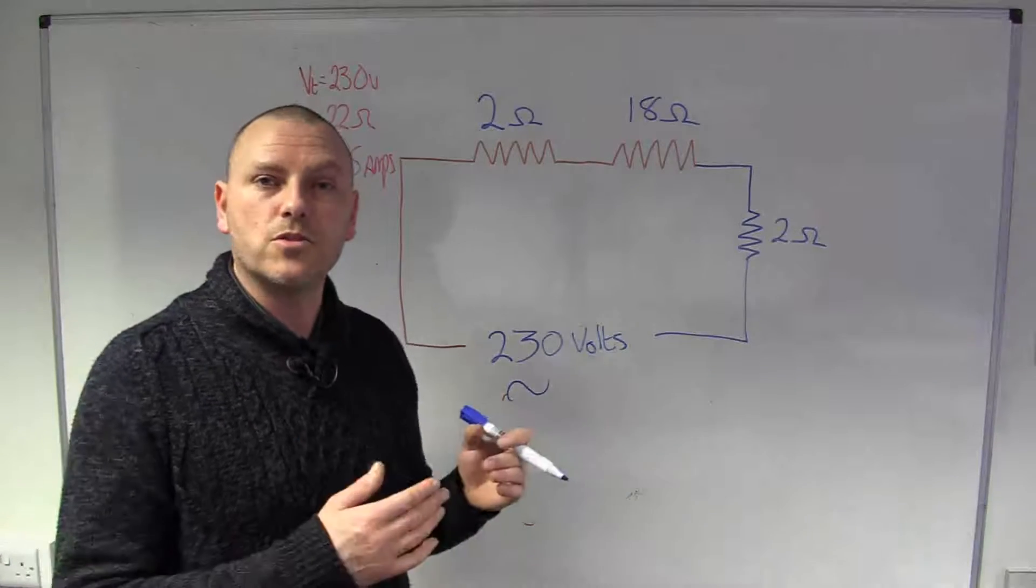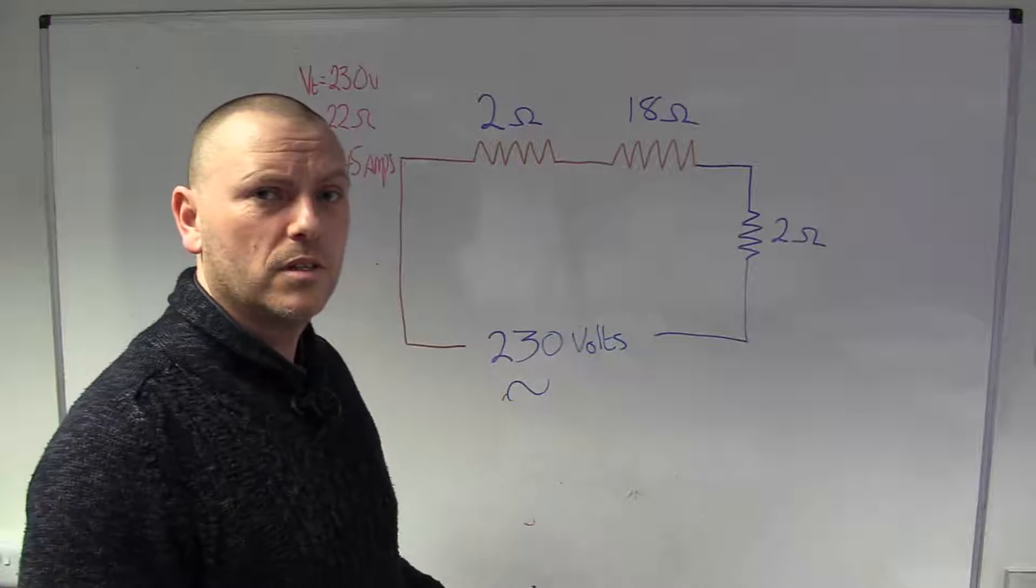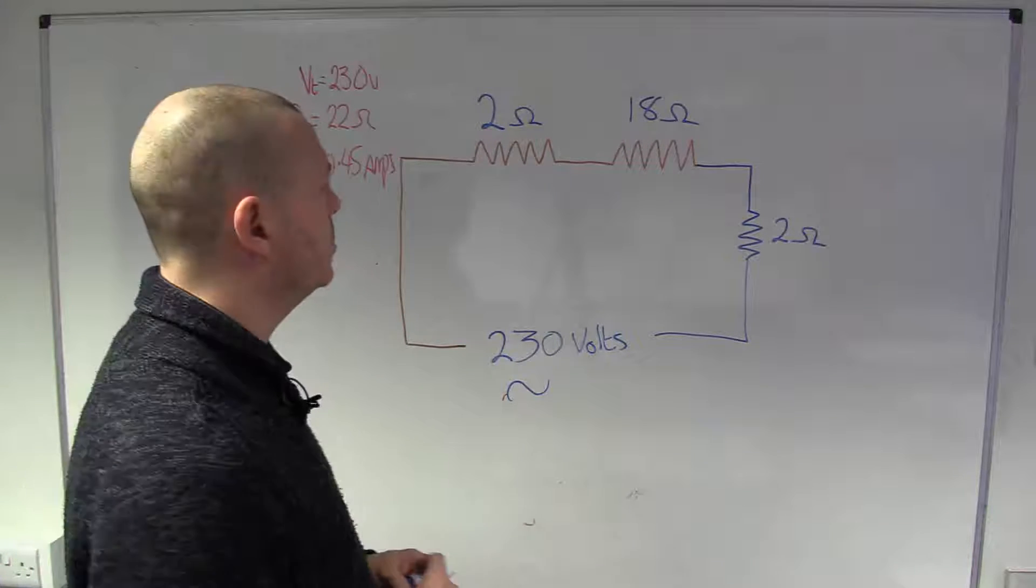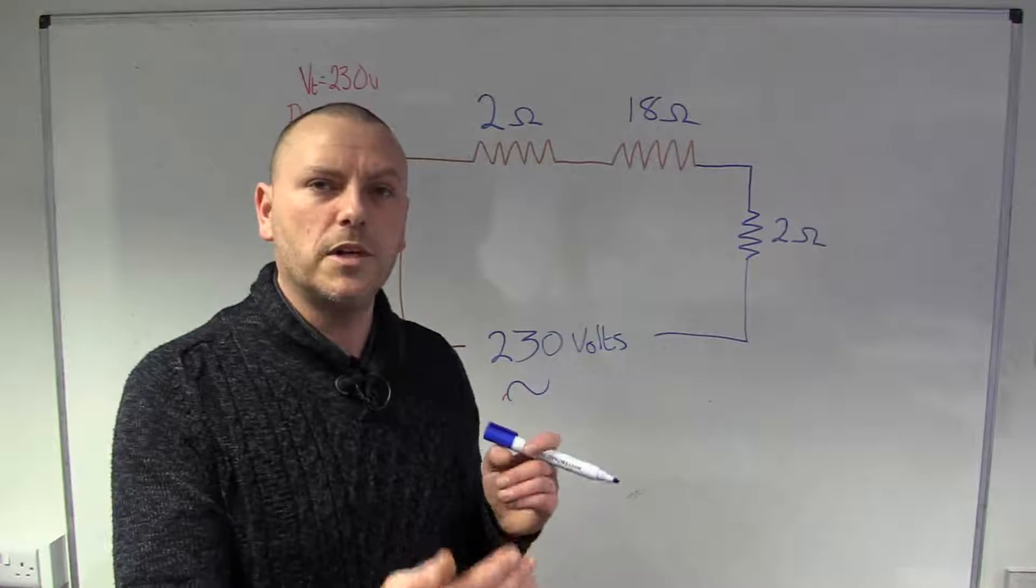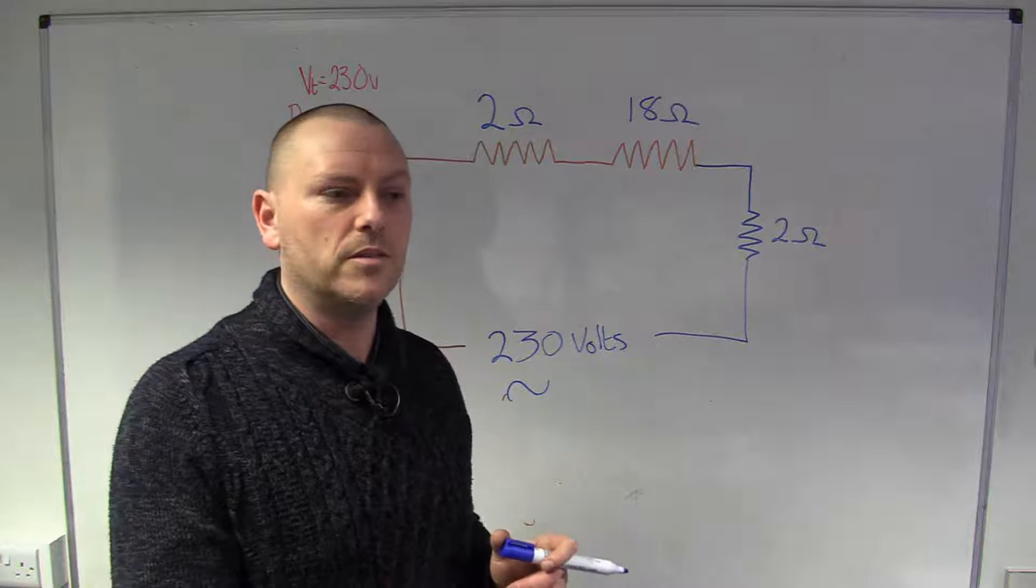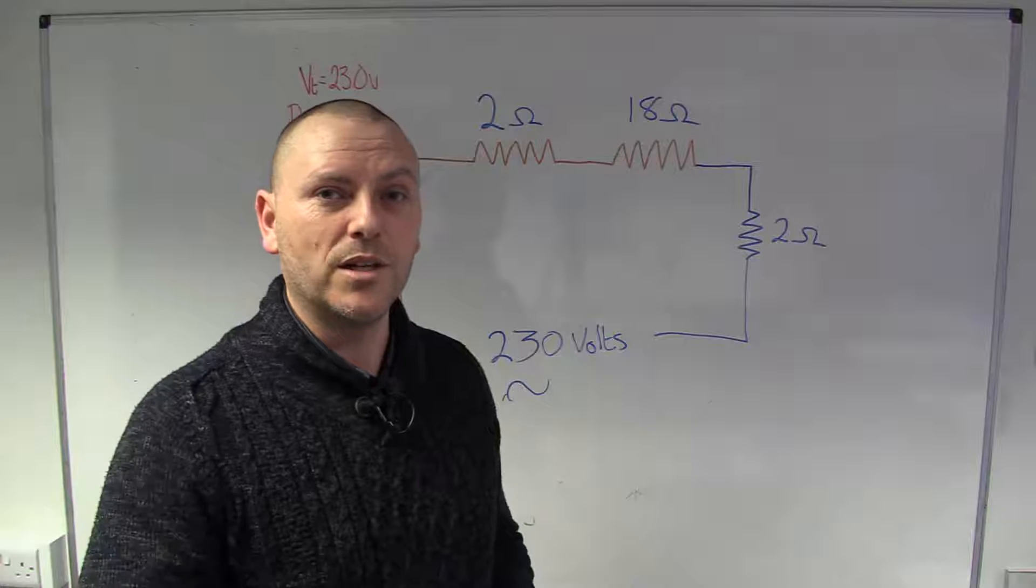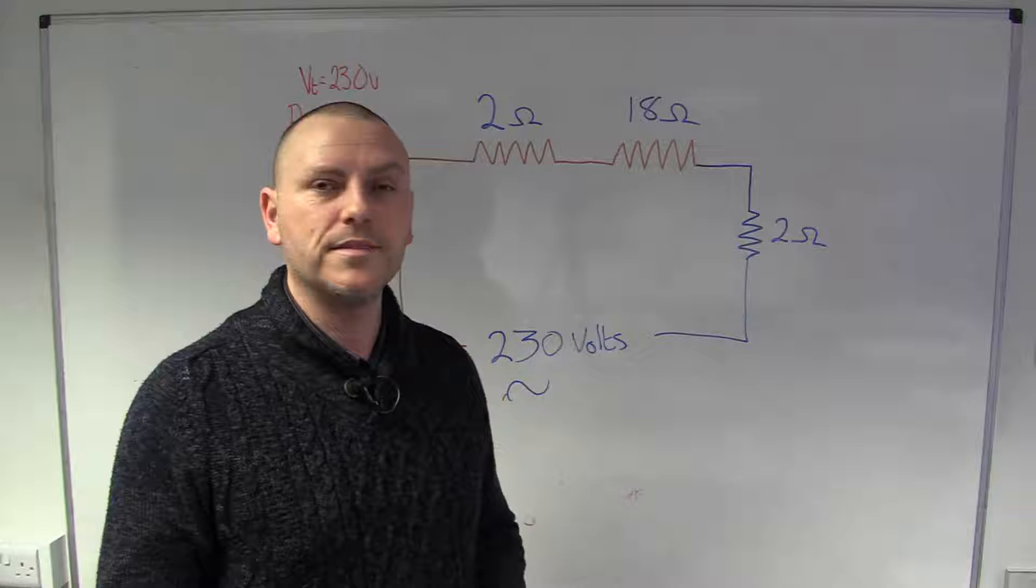So, now we're back to the circuit diagram. Now, sometimes, we're going to need to know the volt drop across a resistor, for many reasons, really. And also, we check volt drop quite a lot in our circuits. It's one of the essential parts of the design sequence, because we want to make sure that our cables don't provide so much resistance to the current flow, that by the time it gets to the thing we're trying to power, we don't actually have enough supply voltage to power it properly.